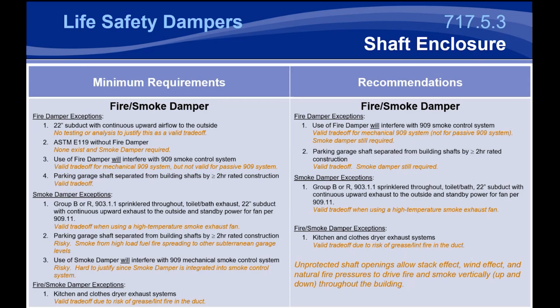We're also seeing an increase in fuel load for these. If it is sprinklered and it is protected, that is certainly a good layer of protection. But what we're seeing with, say, electric car fires these days is there's a huge increase in the amount of water that's needed to extinguish that fire. And because of that, it can be a bit risky with these higher fuel loads in these subterranean parking garages. So it may make sense to keep those dampers in those shafts that are supplying air or exhausting air out of the garage system.